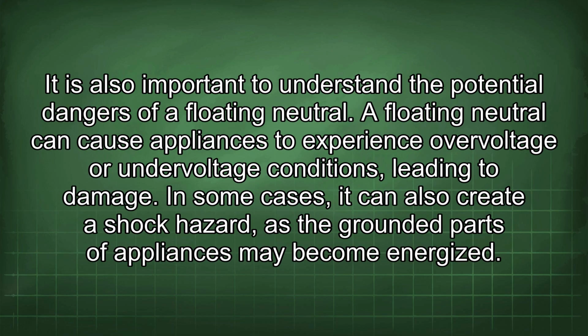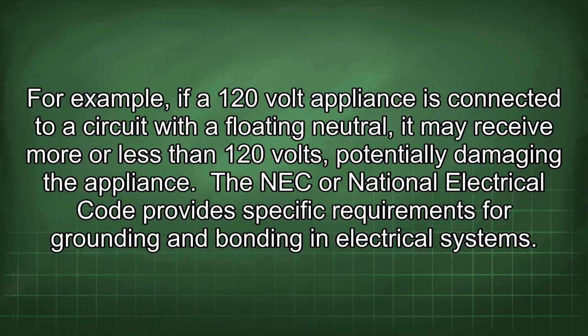It is also important to understand the potential dangers of a floating neutral. A floating neutral can cause appliances to experience overvoltage or undervoltage conditions, leading to damage. In some cases, it can also create a shock hazard, as the grounded parts of appliances may become energized. For example, if a 120-volt appliance is connected to a circuit with a floating neutral, it may receive more or less than 120 volts, potentially damaging the appliance.